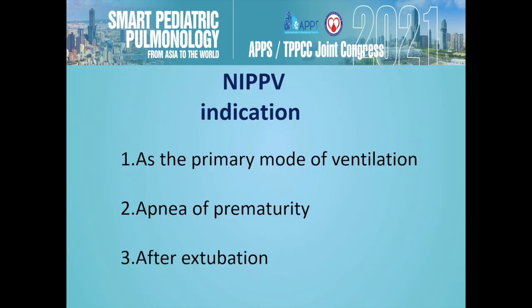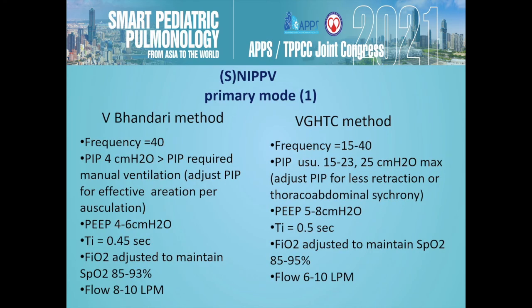Indication. We use NIPV sometimes as the primary mode of ventilation, and also for apnea of prematurity, or after extubation. In primary mode, we use different setting parameters compared with the Bhandari method. We use a low frequency, 15 to 40. Bhandari just uses 40.